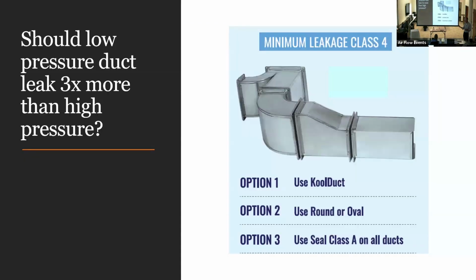Low pressure ductwork. Yeah, you can test more stringently. Other options, as an engineer, you could say, I want all high pressure ductwork everywhere. I want all seal class A. Now, what do you have to do if you're going to specify all seal class A for a contractor? You're going to need to go out and inspect it and make sure, because that may be great. The estimator may estimate all seal class A ductwork, but then the guy in the field gets there and he goes, wait, this is low pressure. I don't have to seal this stuff up. So the communication between the office and the field may not be perfect.